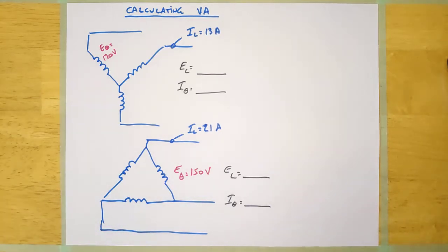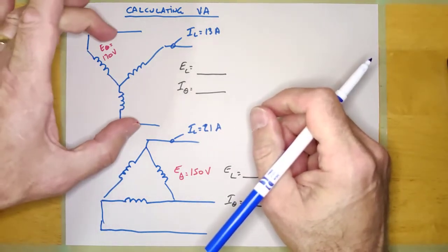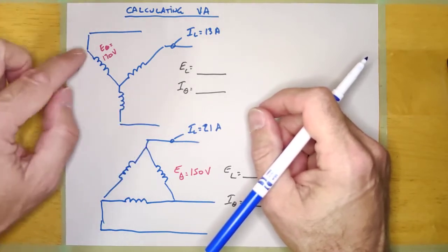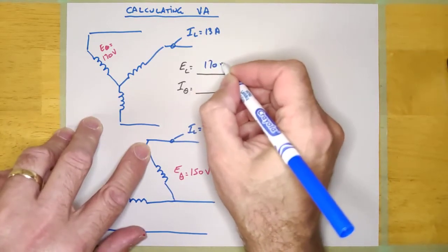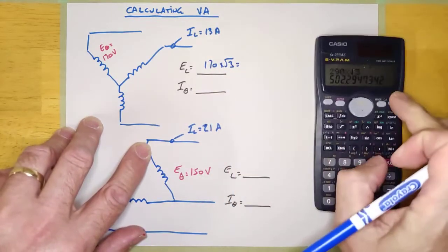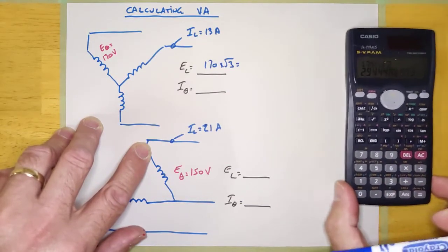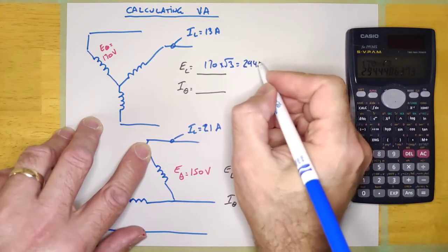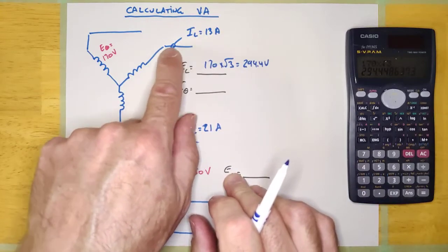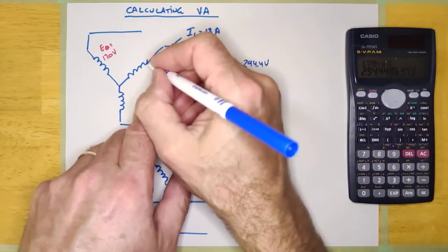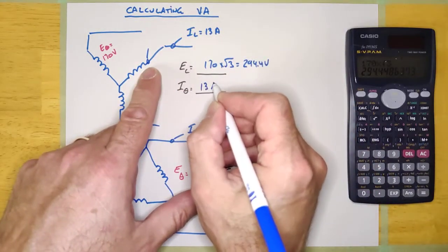We're going to calculate that real quick. There's my phase voltage, and the question is: what is my line voltage? I can see that my line voltage is going to be 170 times root 3, which comes to 294.4 volts. And then for the current — if I clamp on here, it's going to be exactly the same spot, so I_phase is going to be 13 amps.